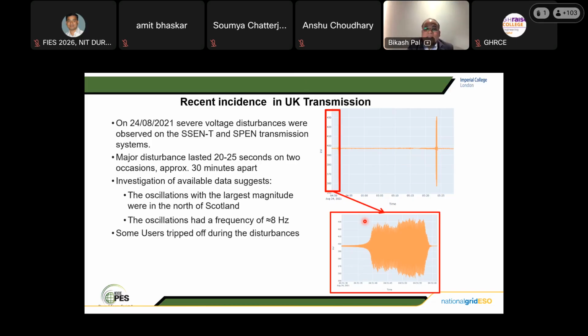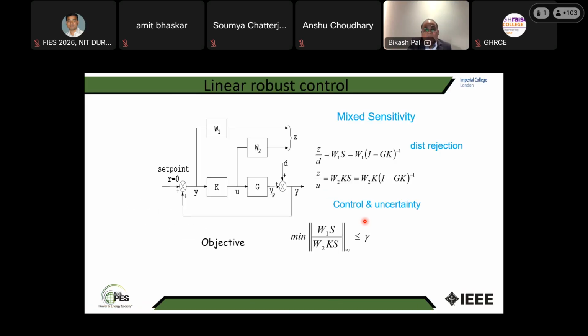So now, with this context, the oscillation frequency dictates the modeling complexity. If the frequency is less than 2 Hz, we can use a phasor approach. If the frequency is more than 2 Hz, you have to go with the electromagnetic approach, or the EMT approach.